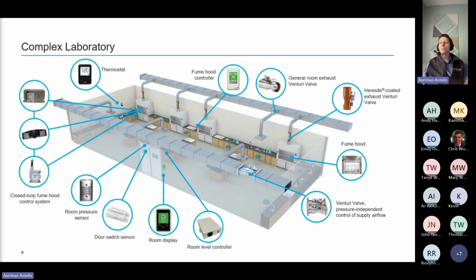Now, on the far end of the spectrum, I'm going to call this the complex laboratory. A complex laboratory is anything that has more than one fume hood, more than one entryway, or some elaborate control sequences that require occupancy or setback modes. In this example, I'm showing 4 individual fume hoods. Each fume hood is like a mini room in itself. It's got its own workspace. It's got its own air change requirements in its workspace, and it's got its own dedicated fume hood controller to manage all of those requirements.